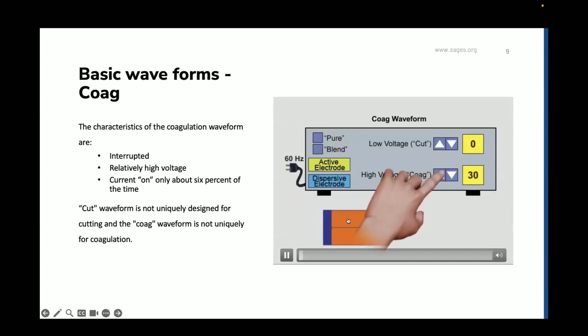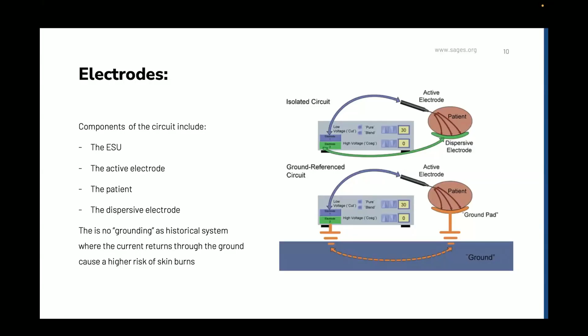Electrodes. So each circuit, in essence, has four basic components: the ESU itself, the active electrode, the patient, and then the dispersive electrode. There is no grounding because none of the current is being delivered back through the ground. This is a historic system that hasn't been used in decades, because it could lead to higher risk of current diversion and burns.